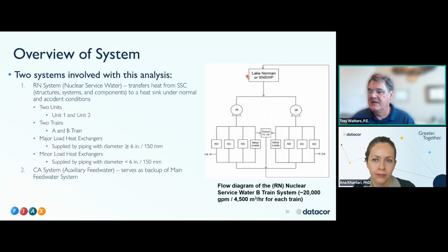So the power plant at Duke McGuire is right next to Lake Norman. But if there was an issue with the lake, then they had a pond that they could pull water from. But primarily they pulled water from Lake Norman. I'll show you in a moment what that looked like as far as what it did to their pipes. And then the pumps came in, and they had a whole bunch of heat exchangers. I'll show you a little bit later, but they call these the major heat exchanger loads.